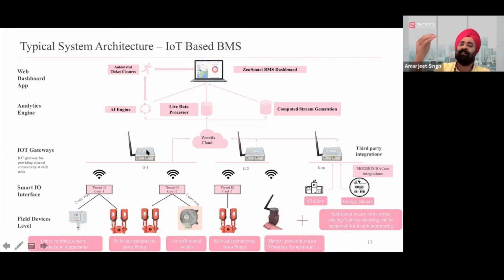Answering the question of what happens if systems get disconnected: there are three levels of redundancy built into the system. First, if the IO cards get disconnected, they have their own local PID logic running locally. Second, the wireless mesh is self-healing, so even if some nodes go down, the rest recreate the mesh.